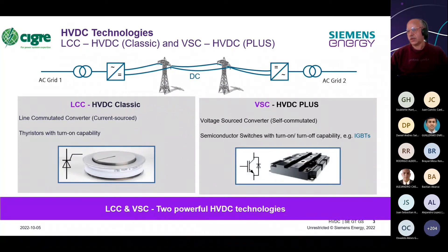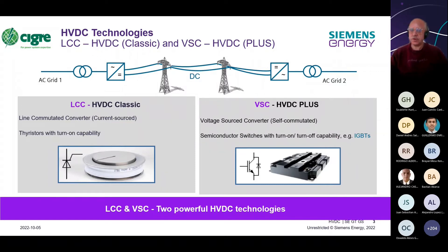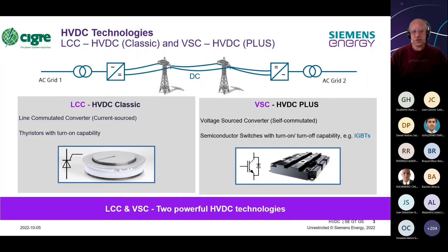In HVDC, there are two technologies currently available. The first is Line Commutated Converters (LCC) using thyristor valves as the switching device — a well-established technology for almost six decades. The other, developed over the last one and a half decades, is Voltage Source Converters (VSC), also called HVDC Plus in Siemens terminology, which uses IGBTs as the main switching device.